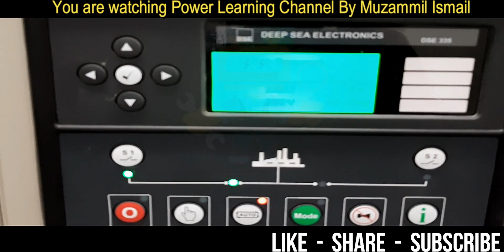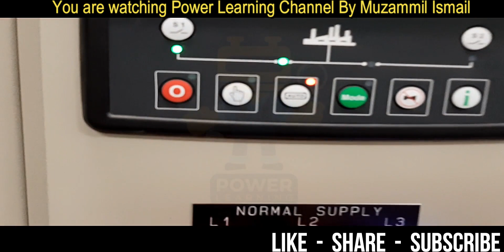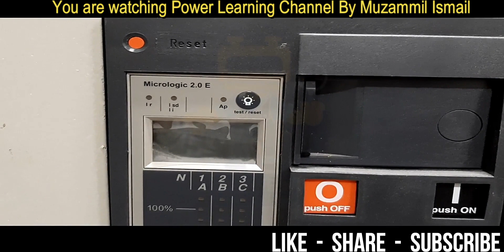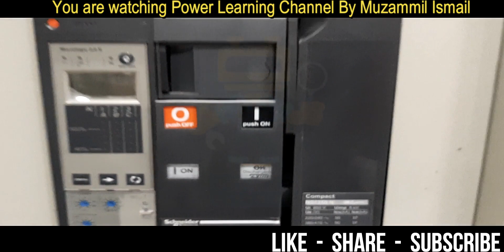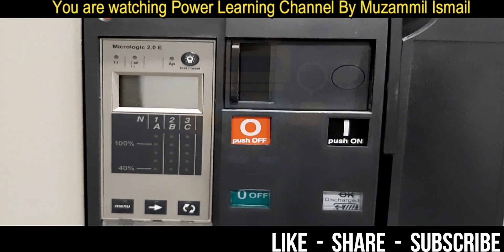Let's get started. So guys, now we are at the site, and you can see the digital controller display is on, the power is on. S1 is closed, showing S1 closed and no start request. The normal supply is available, QN is on, generator supply is off, QG is off, and load is available. S1 shows the power is on and there is no S2 supply - S2 is our generator. This first breaker QN is for the main transformer supply, and it is on now, so the load is on the transformer. The second breaker QG is used for the generator.